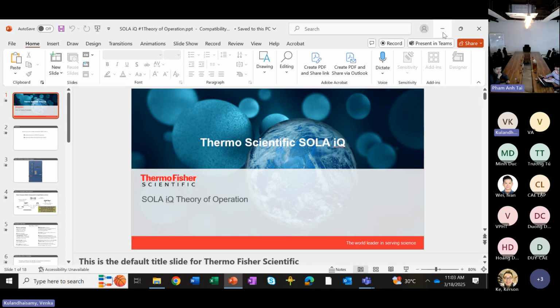But the only thing is, they cannot do auto calibration. Even though they have the software, the calibration has to be done manually. It's the same as SOLA 2. So the difference is only that the operating software is different, and the internal electronic parts are all different. But the principle of operation is exactly the same as SOLA 2. There is no difference. So this SOLA IQ can replace SOLA 2, no problem. The only thing is, the customer is not able to use the Lookout software for SOLA IQ.